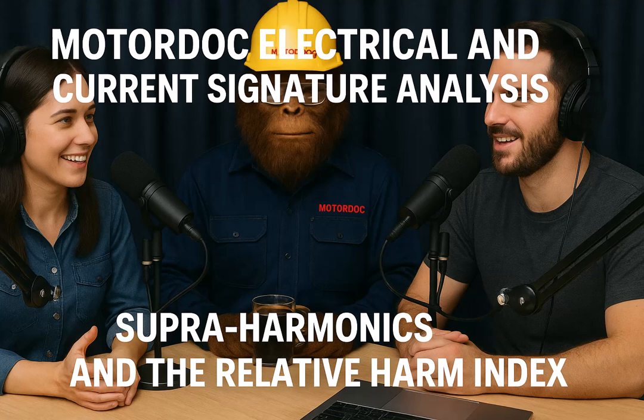And these currents can be quite high, even on the ground paths. Surprisingly high, yeah. Research found currents up to 150 amps on the main bearing ground connection in some cases. 150 amps, even though the main grounding is for lightning. Exactly. And interestingly, the frequencies of these circulating currents in the nacelle, often related to the generator's operation, can be different from the grid frequency you'd measure down at the tower base.